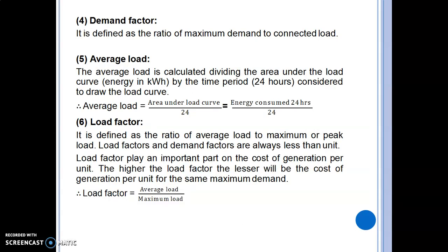The demand factor is defined as the ratio of maximum demand to the connected load. The average load is calculated by dividing the area under the load curve by the time period considered. The area under the load curve represents the energy consumed in 24 hours for a daily load curve. Dividing this energy by the time duration gives the average load.